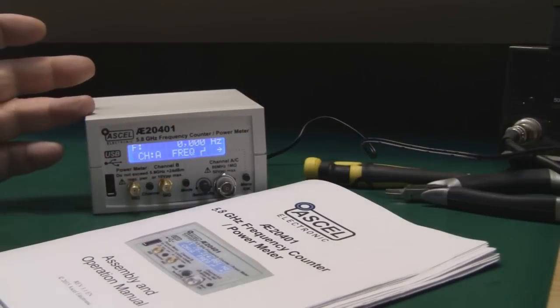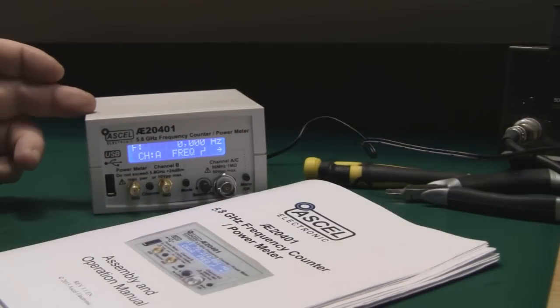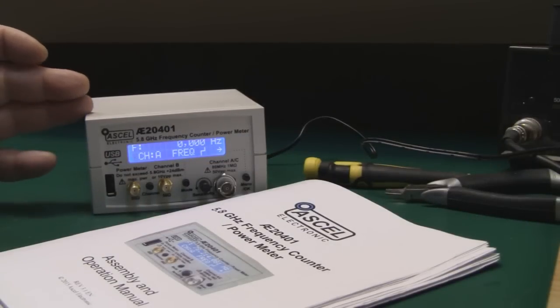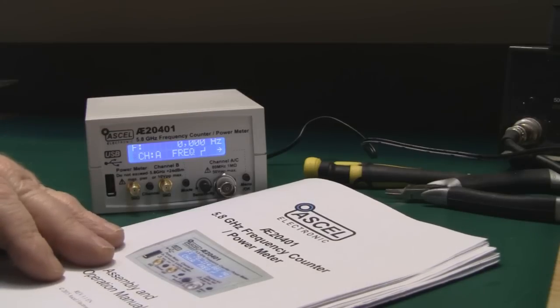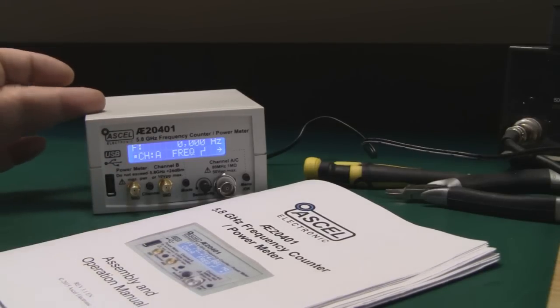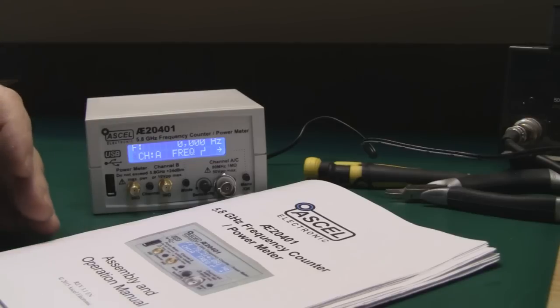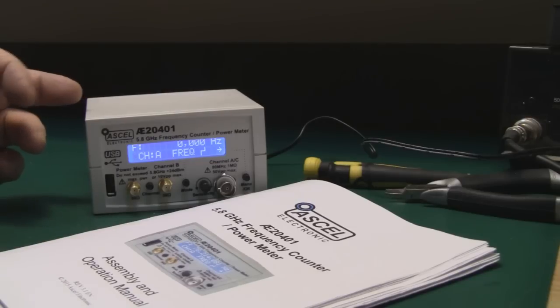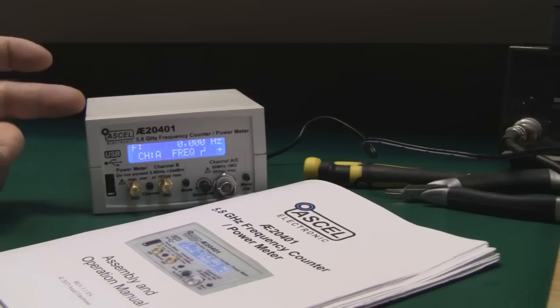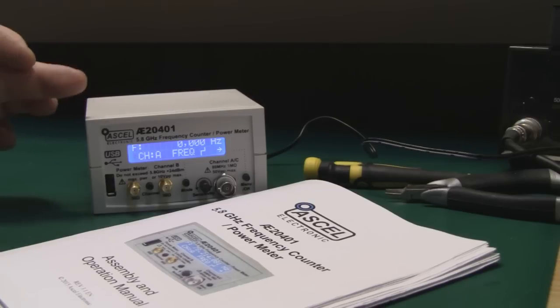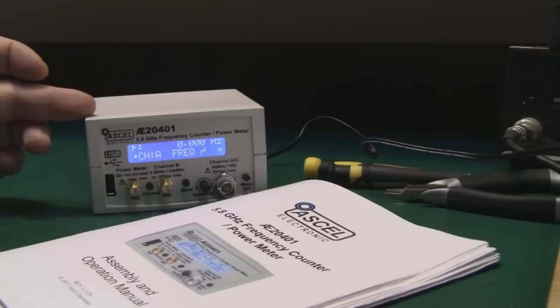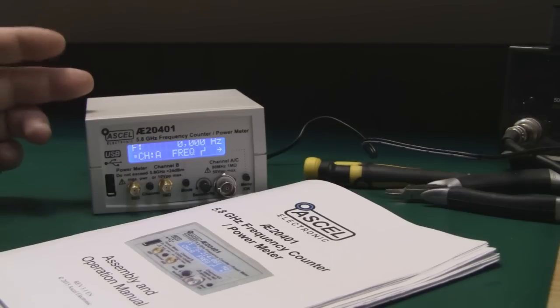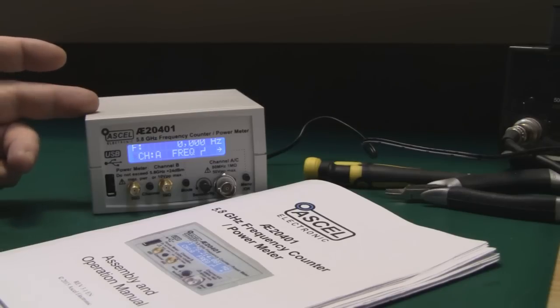What I'm going to do is leave this video here and do a part two, because I want to have a proper read through this manual and I also need to calibrate this. According to the manual there's two ways of calibrating it - one using a multimeter and one using an oscilloscope. The preferred method is to use an oscilloscope because it says it's a much more accurate way to calibrate this.